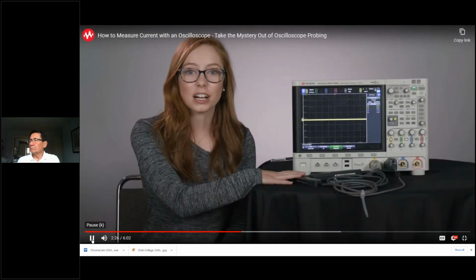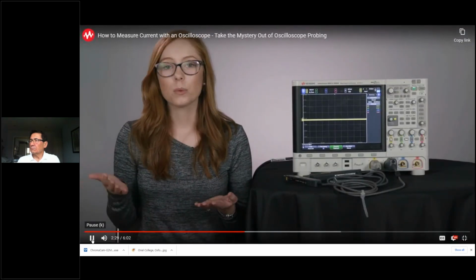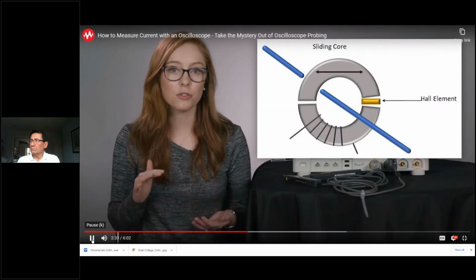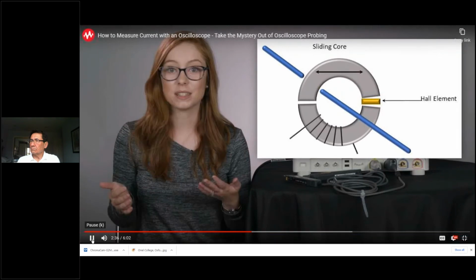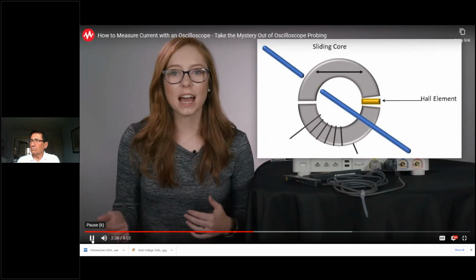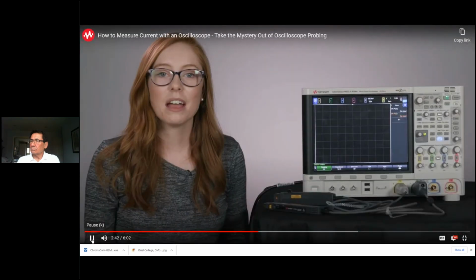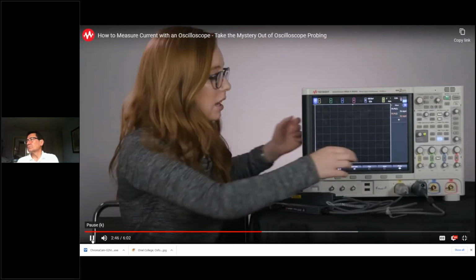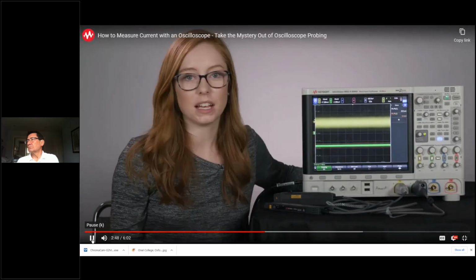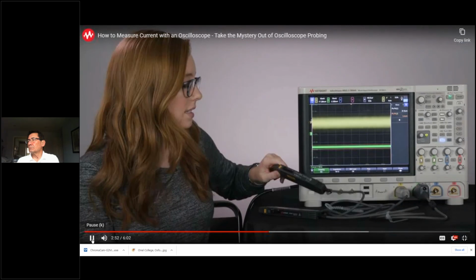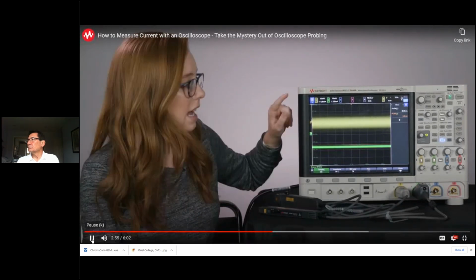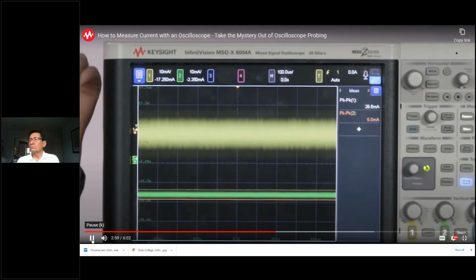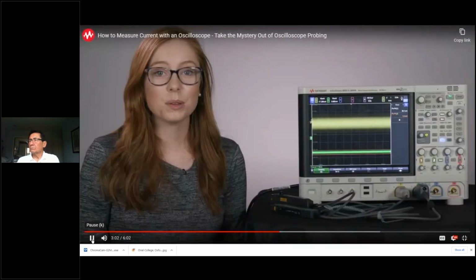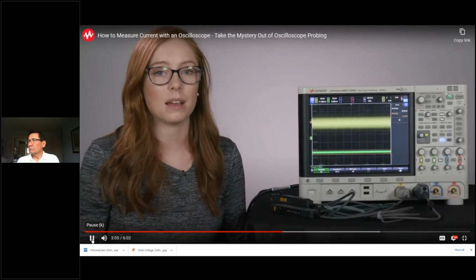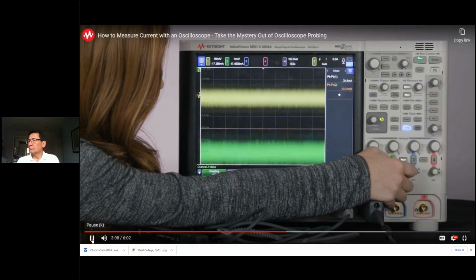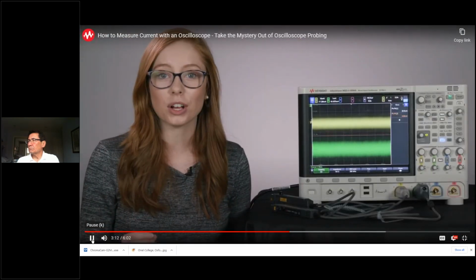And these clamp-on style current probes have a hybrid AC-DC measurement technology, which means that they have both a Hall effect sensor element for measuring low-frequency DC contents and a current transformer for measuring those AC contents. So you're able to account for the DC offset of your signal instead of the probe blocking it out. Let's look at an example. I have a couple different clamp-on style current probes plugged into channel 1 and 2. Let's just take a look at the baseline noise of these two probes. On channel 1, I have an older Keysight probe that has a 10-to-1 conversion factor. This means that we're only able to go down to 10 milliamps per division on the vertical setting. And this really isn't good enough for most low-level current measurements. But with the probe on channel 2, we can actually go down to 1 milliamp per division.